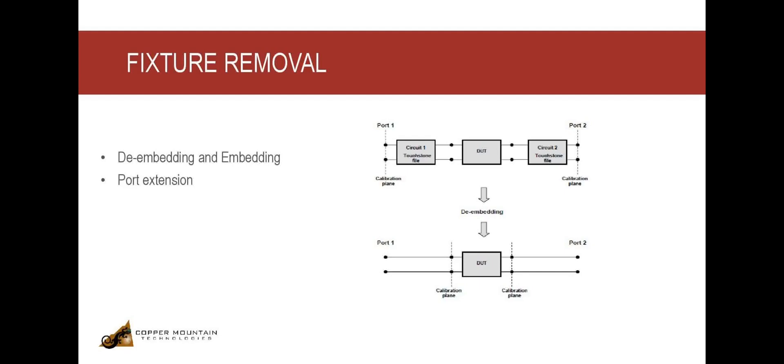There is another simpler way to de-embed a fixture, and that is with the help of the port extension function. This function virtually extends the test ports by moving the calibration plane to the terminals of the DUT.